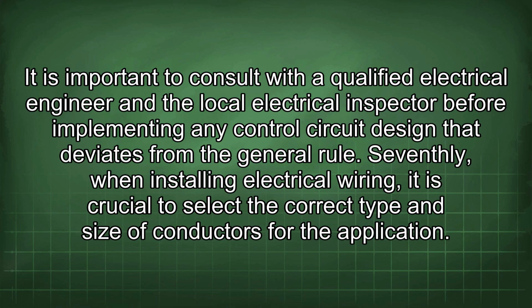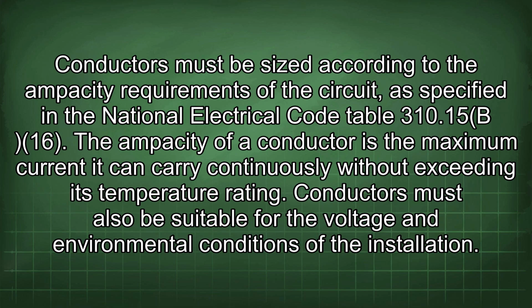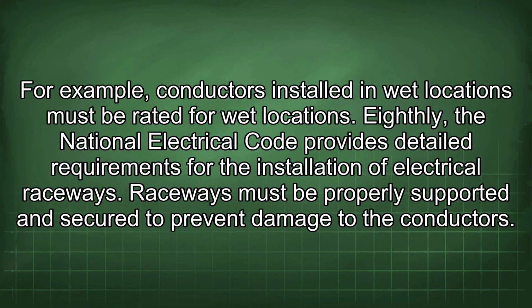Seventhly, when installing electrical wiring, it is crucial to select the correct type and size of conductors for the application. Conductors must be sized according to the ampacity requirements of the circuit, as specified in National Electrical Code Table 310.15(B)(16). The ampacity of a conductor is the maximum current it can carry continuously without exceeding its temperature rating. Conductors must also be suitable for the voltage and environmental conditions of the installation. For example, conductors installed in wet locations must be rated for wet locations.